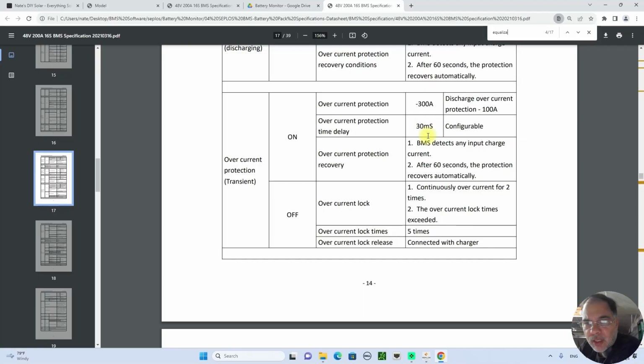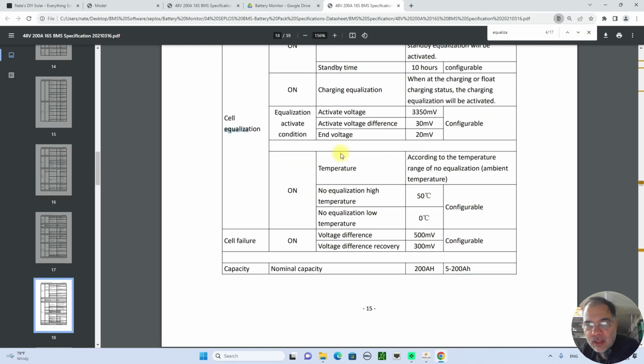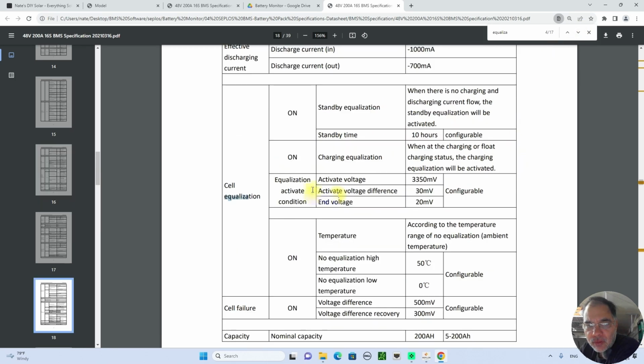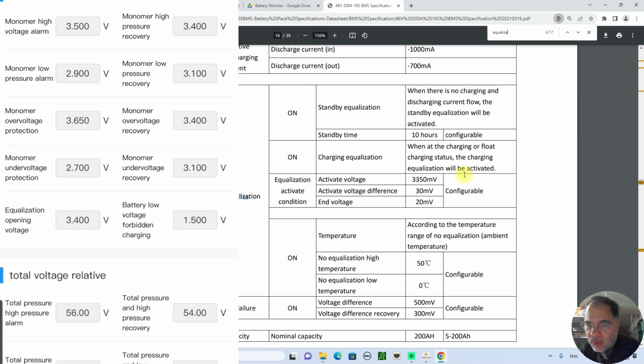So the first thing we come to is cell equalization. Equalization activate condition, activate voltage 3.35 volts. So they actually have it set to 3.40, which is good - that's typically where I like the balancer to start balancing.